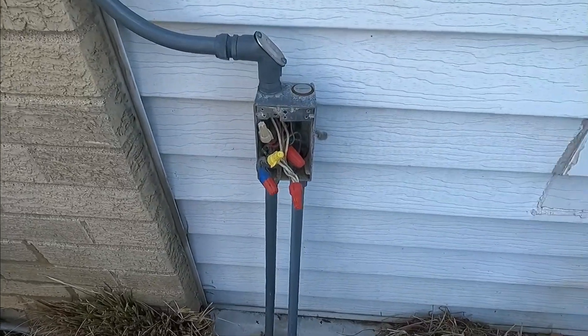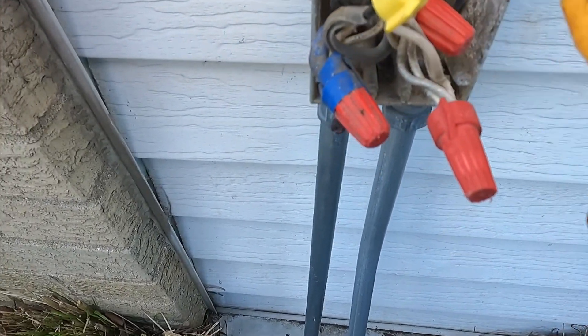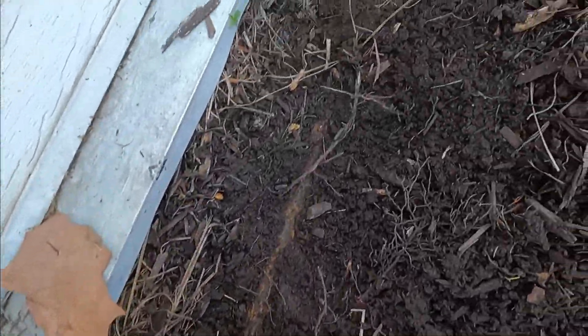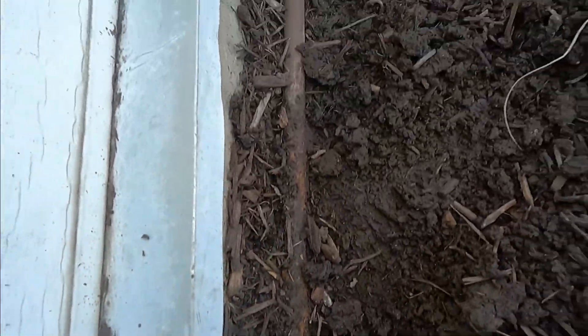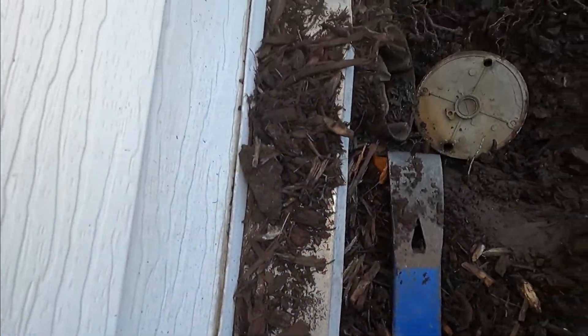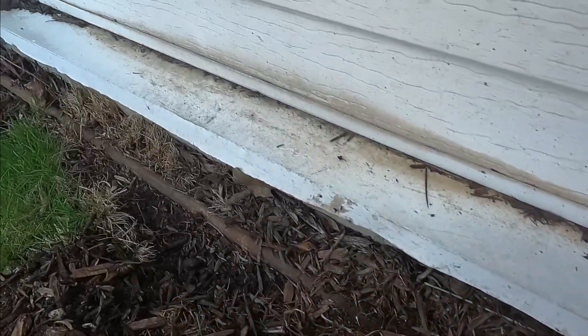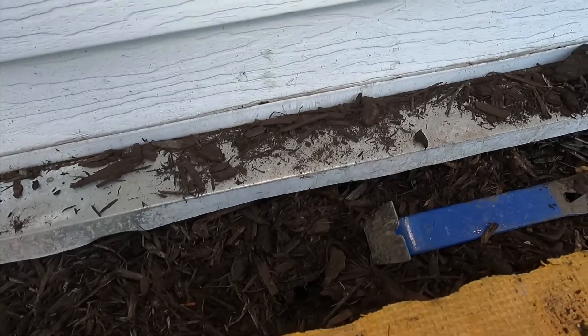One more time — this is our feed and we have power here. This is a number 12 gauge wire that goes through that pipe. You can see the pipe right there, it's rusted right there, and it goes that way, then right there, and then it comes here. This is my blue wire, but there's no power there. The pipe looks solid, but there's no power from point A to point B.